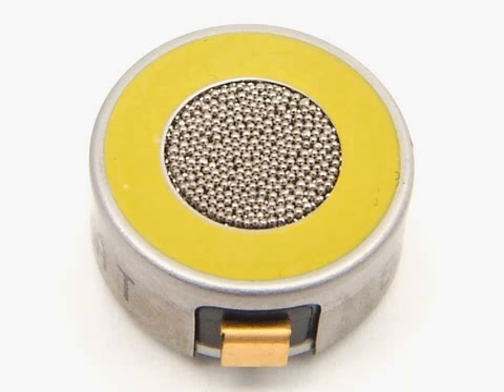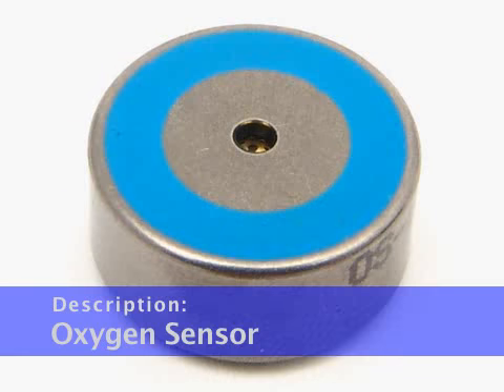The current is amplified by the GX-2009 circuitry, converted to a measurement of combustible gas concentration, and displayed on the LCD. The oxygen sensor is a galvanic type sensor. A membrane covers the cell and allows gas to diffuse into the cell at a rate proportional to the partial pressure of oxygen. The oxygen reacts in the cell and produces a voltage proportional to the concentration of oxygen. The voltage is measured by the GX-2009 circuitry, converted to a measurement of gas concentration, and displayed on the LCD display.